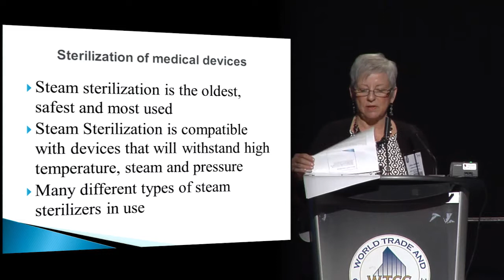Just saying. So the steam sterilization technician must be really knowledgeable in all the phases of steam sterilization. And as Linda indicated, there's a lot of steps that take place before you get to put it into the sterilizers, and they're very clean, very clear. If you can't clean it, you cannot sterilize it. So it's about as simple as that. You know, to be successful in the next steps, it has to be clean. And of course, there are many different types and sizes of sterilizers. I'm going to quickly go over the different types and how they work.